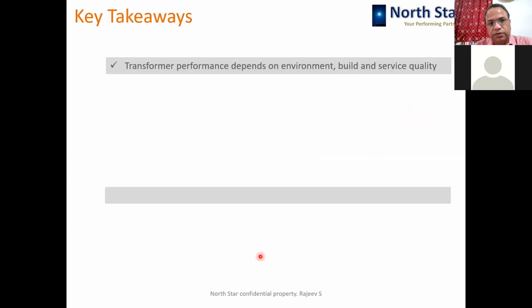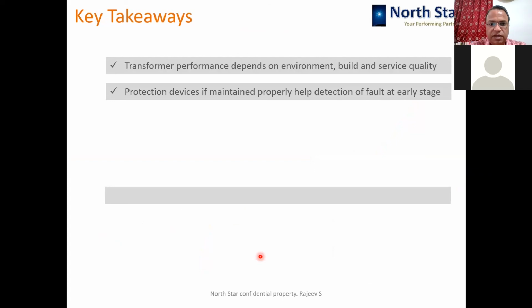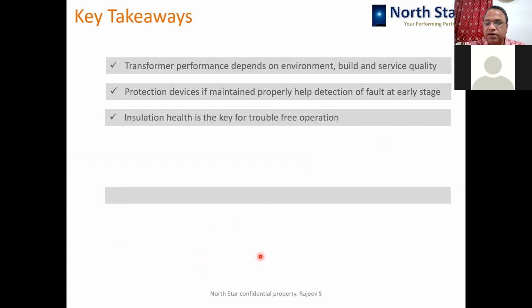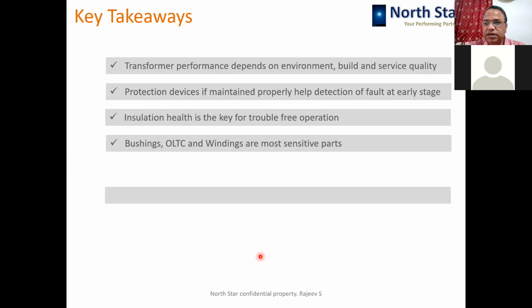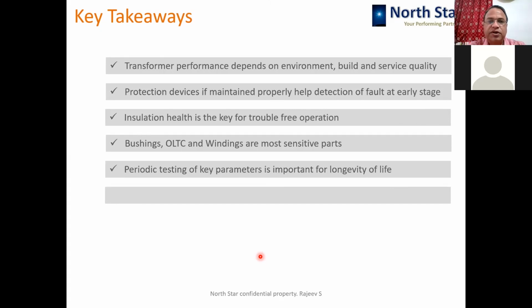So the key takeaways from today's program are: transformer performance depends on environment, build and service quality. These three are the performance factors of the transformer. Protection devices must be maintained properly, as they help detect faults at a very early stage. Insulation health is the key for trouble-free operation. Bushing, OLTC, and windings are the most sensitive parts, and they fail more often, so good care has to be taken of these. Then periodic, comprehensive testing has to be performed from time to time.